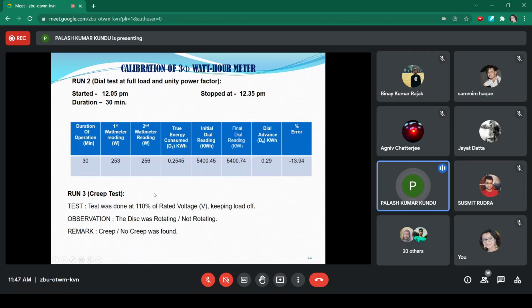In run 3, that is the creep test, no creep has been observed, because when the energy meter is released by the manufacturer, creep should be avoided. Any creep should be eliminated by taking proper care. So no creep was found in our case.